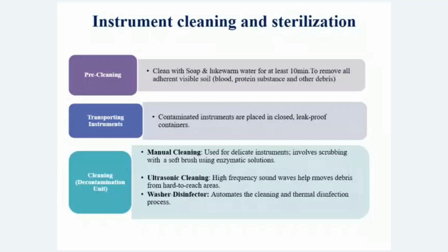Now you need to have an instrument cleaning area. The instrument has to be cleaned with soap and lukewarm water for at least 10 minutes to remove all the adherent visible soil. If you don't remove all these visible soil, the blood and other debris, it cannot be sterilized properly. The sterilization will not be effective. Hence, it has to be immediately washed and cleaned.